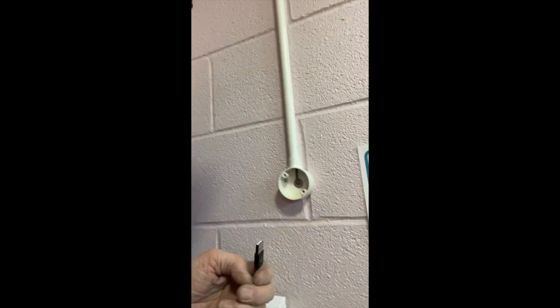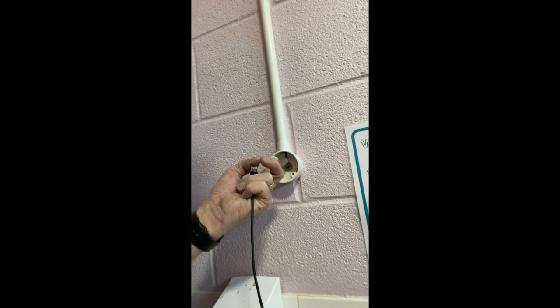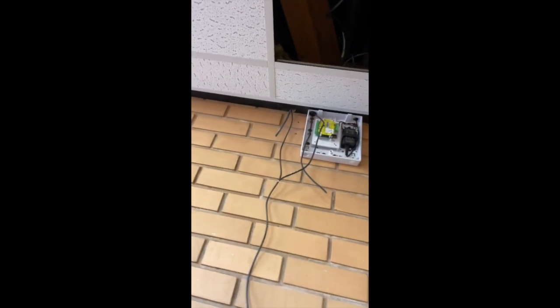It's all low voltage, extra low voltage cable. It's just a reader. It's just data. So that goes all the way up into the ceiling, over the top, then comes back to those 2 cables coming out the top of that. I've moved the mains over. It's going to have its own fuse spur now, just as a means of isolating one from the other, rather than pulling the plug and everything going off.